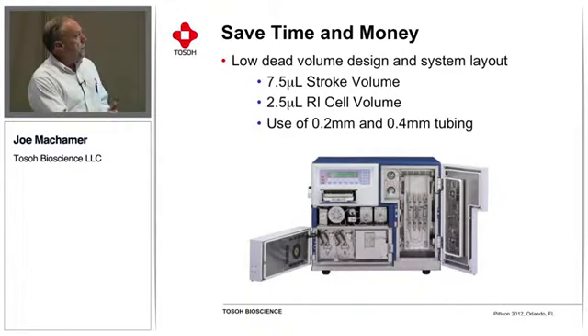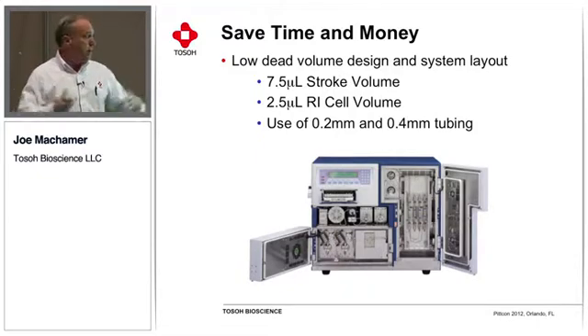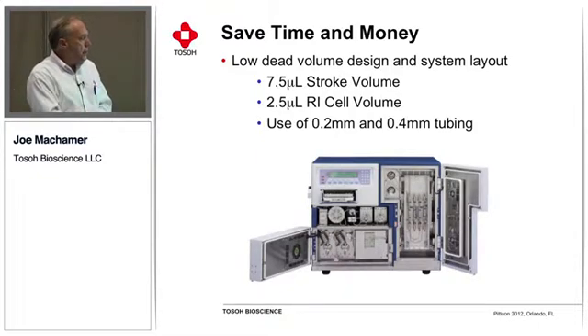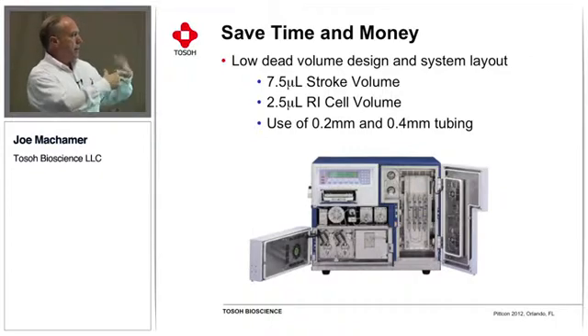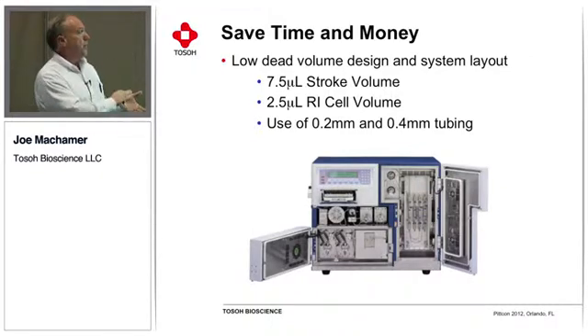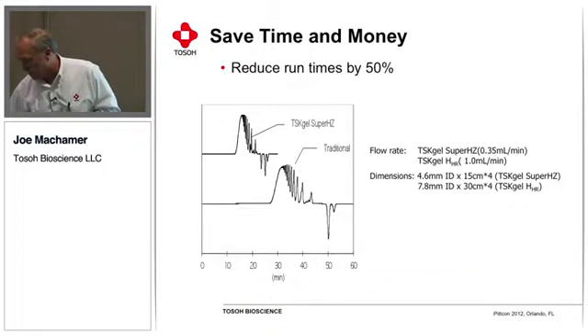and part of the reason that we get this low dead volume is the design of the system, where all of the components are essentially in one box, if you will. And so that lets us place the individual components very, very close to each other so we can use very, very short lengths of tubing. We also use a very low volume in our flow cells, and the combination of all that is, when you run very small columns on this instrument, you're able to maintain good resolution.